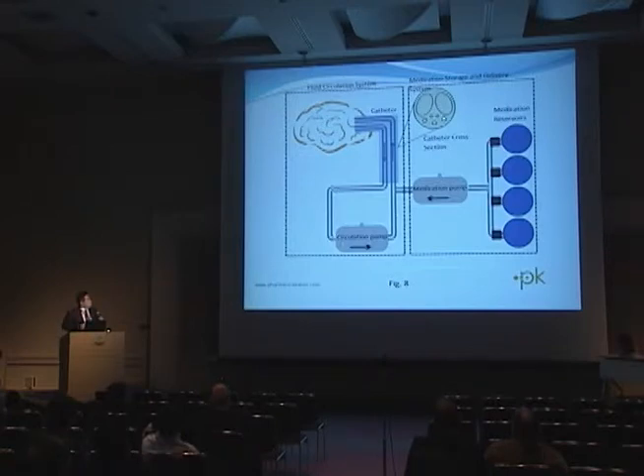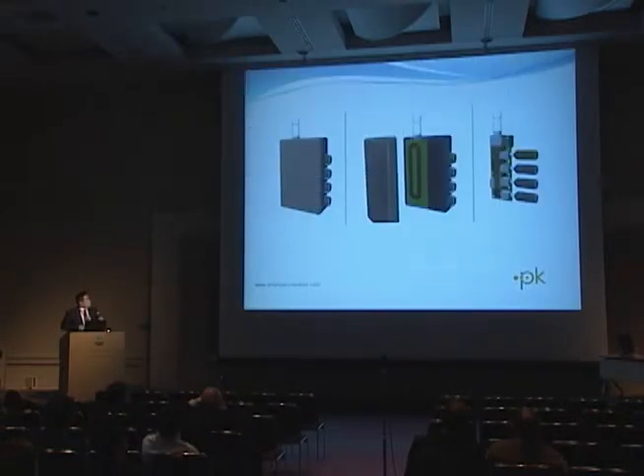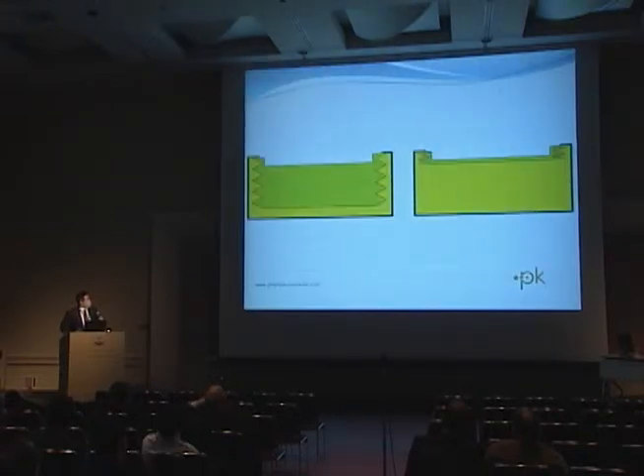So you can see with the cross section that there are 2 delivery pumps, 2 delivery lumens, as well as sensors within the catheter. And this is the pump itself, the canisters that are involved, and these will be powered by a piezoelectric pump. And this is the bellow system that's going to be responsible for delivering chemotherapy. As you deliver chemotherapy, you develop negative pressure, so the bellow system is needed to maintain constant delivery of chemotherapy.